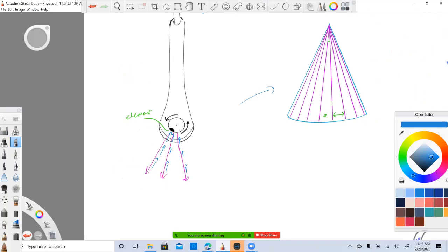So this is called mechanical steering. We don't have in our lab any mechanically steered or mechanical transducers. I have used them in the kind of distant past, and I haven't had my hand on one in, well, certainly more than a decade. Focusing is fixed. And that could be internal or external.